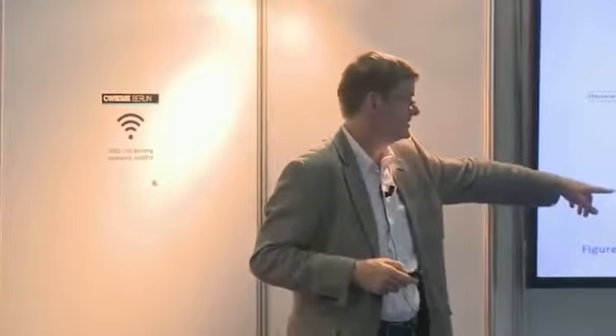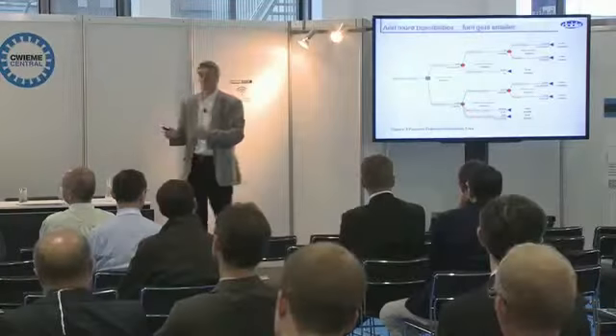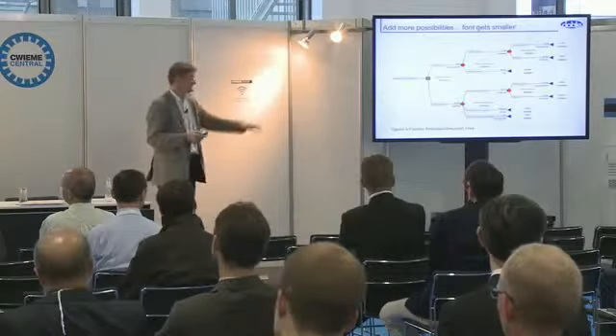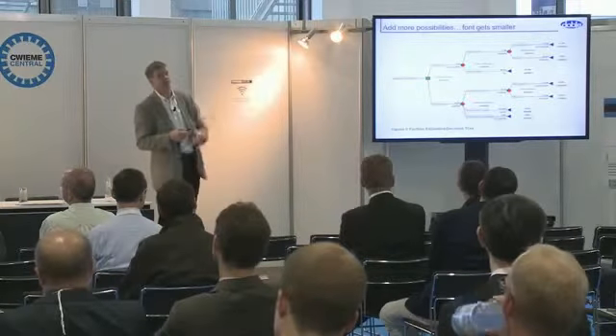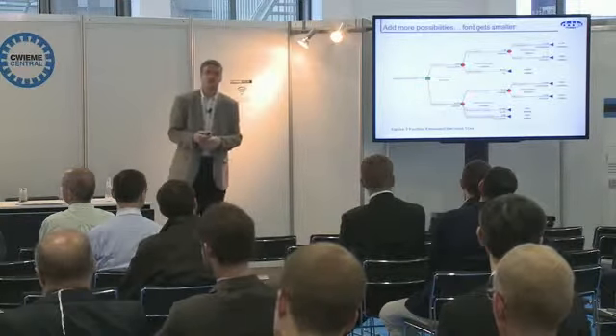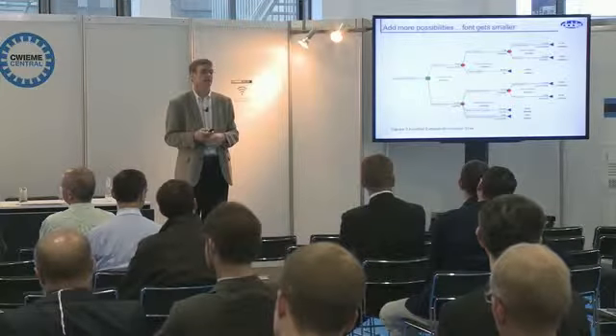But you can upset that because the refurbish decision is made on site. We'll take the transformer back to the factory, check it out, and fix it. There is a chance, new bottom line, that it's not in fact repairable. Just a small chance, say 1 in 20, 1 in 30. You add that in, and now the decision to refurbish is no good. You need to get a new one.